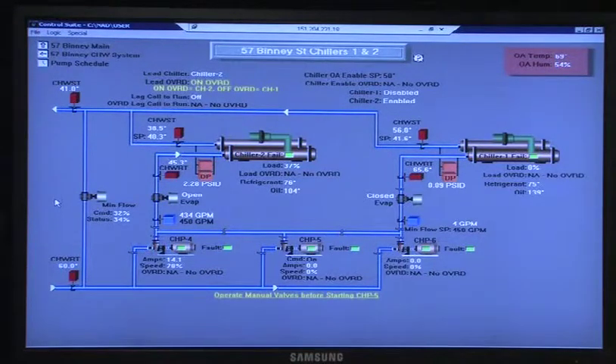A little history on this chiller. With the minimum flow, like Steve said, you're trying to maintain 450 GPM through the chiller. If both chillers are running, with two sets of pumps running, it's going to take the lowest flow of either, so the valve will control to maintain the lower flow. So if chiller 2 has 600 and chiller 1 has 300, it's going to open up to get flow to maintain that one.